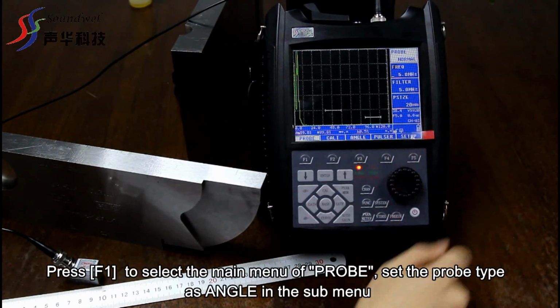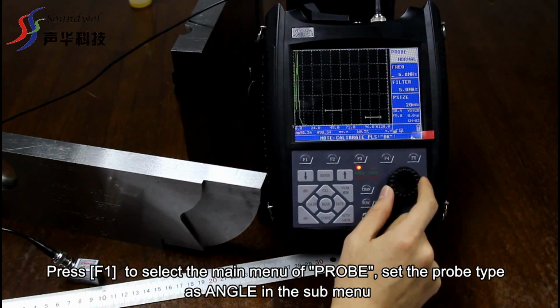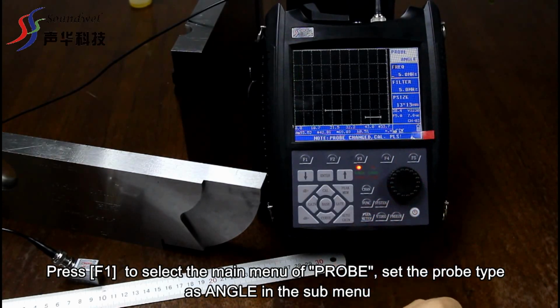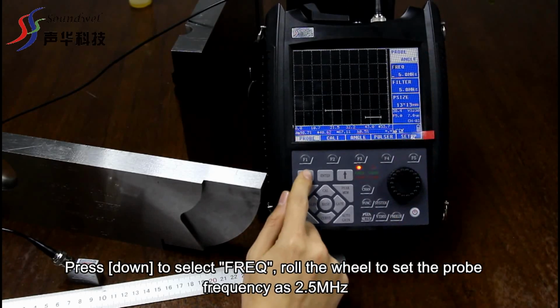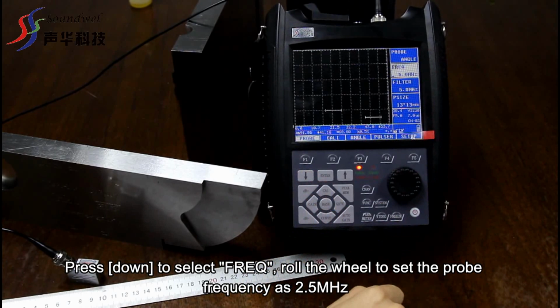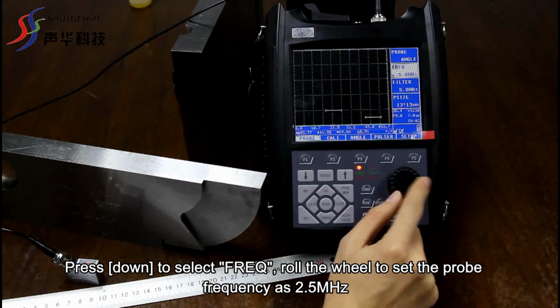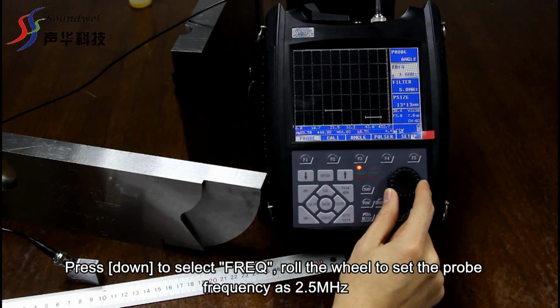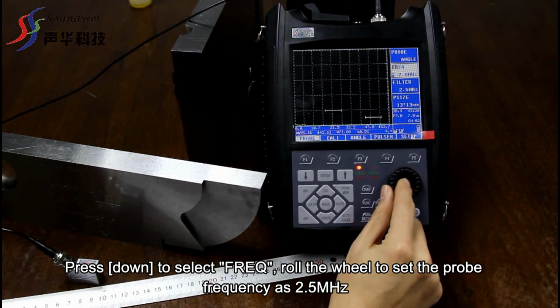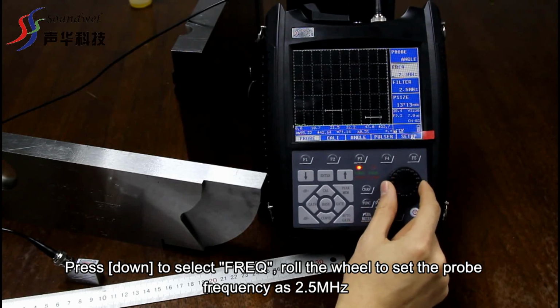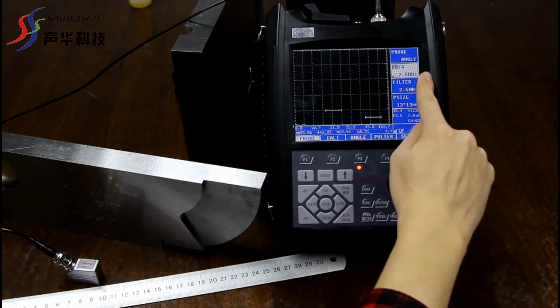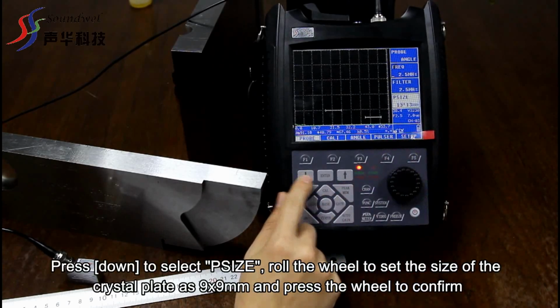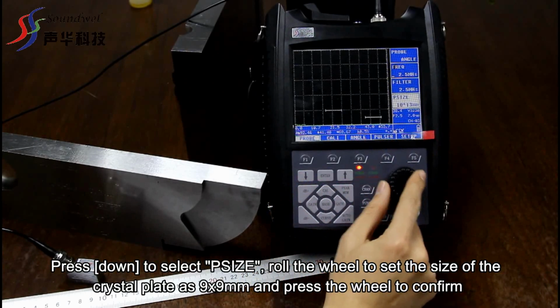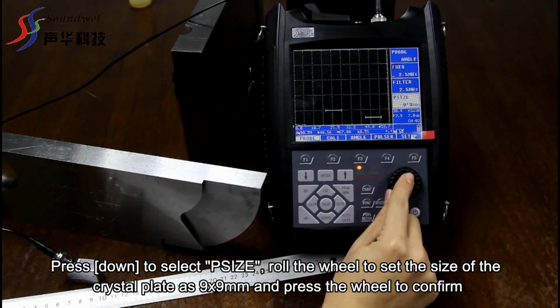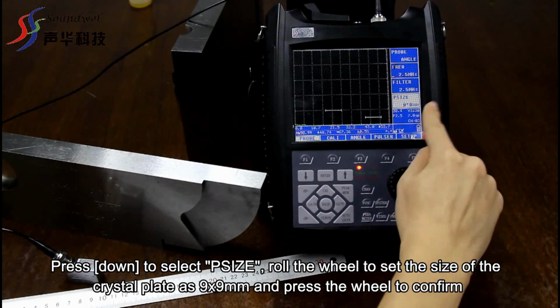Press F1 to select the main menu of Probe. Set the probe type as Angle in the submenu. Press down to select Freq. Roll the wheel to set the probe frequency as 2.5 MHz. Press down to select P-size. Roll the wheel to set the size of the crystal plate as 9 by 9 millimeters, and press the wheel to confirm.